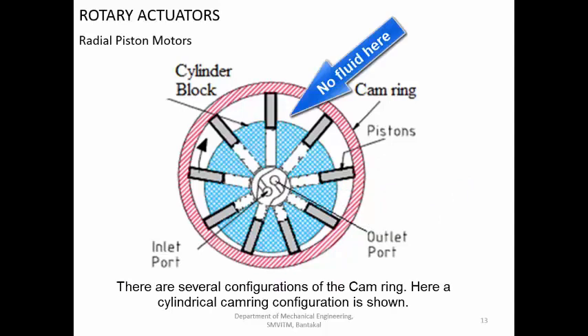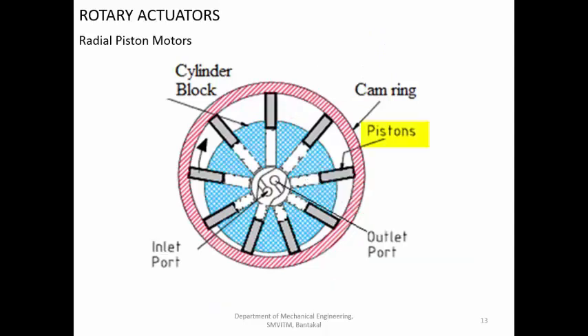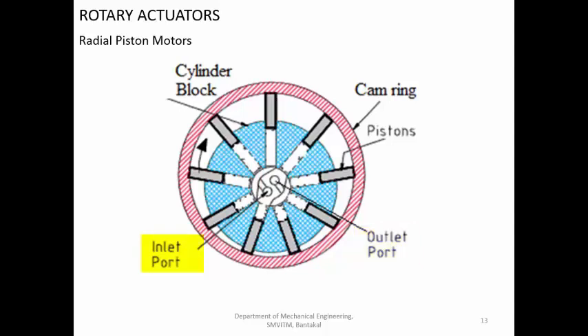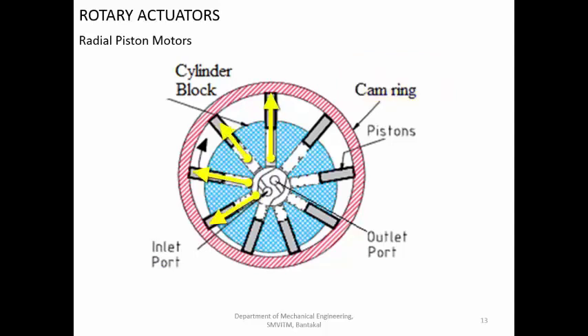The fluid is present only on one side — this will be the cylinder. They will be round shaped pistons and the motion of the piston is in the radial direction with respect to the axis of the motor, which is why it is called a radial piston motor. On the cylinder block you will have usually an odd number of pistons, and you are having the inlet and outlet ports present at the center. Fluid comes here, acts on different pistons, and the pistons move outward. Because of the tangential component of force along the inner surface of the casing, the pistons try to move, and along with the piston the cylinder block and drive shaft rotate. Among the piston motors, the radial piston motor can generate the maximum amount of torque. The speed of operation is moderate but the torque development is maximum.